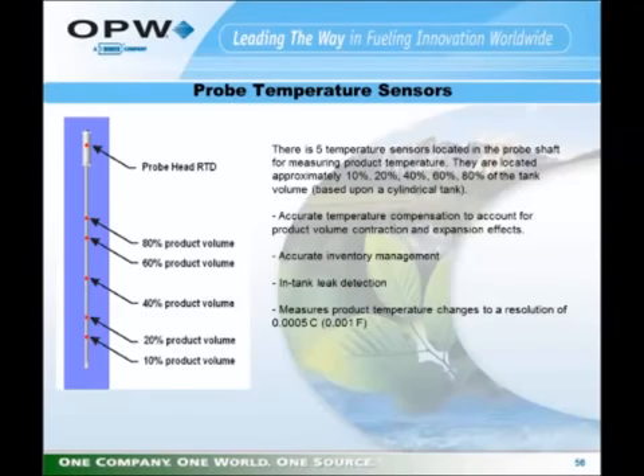The probe temperature sensors, there are 5 of them along the probe shaft, and there's an additional probe head RTD that's used as a reference. So the probe sensor RTD sensors are normally installed at 10%, 20%, 40%, 60%, and 80% of the length of the probe shaft. They're used to determine the average product temperature so that the tank gauge can then generate a temperature corrected net volume for the product that's being measured.